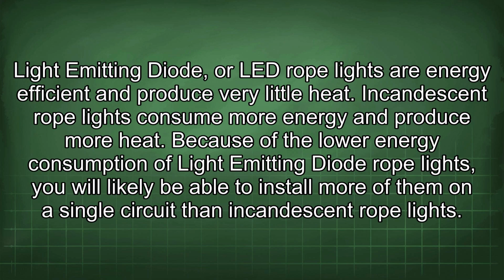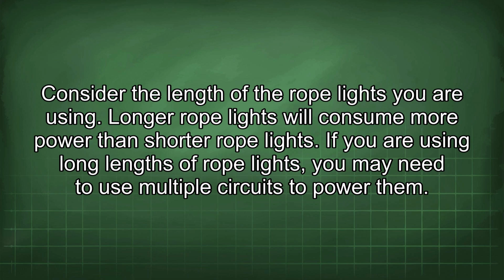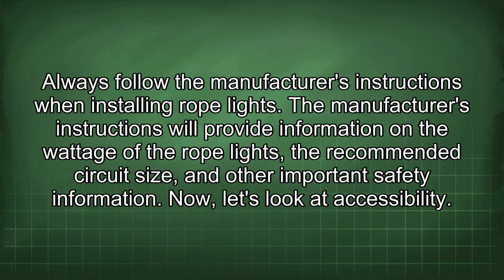Light-emitting diode or LED rope lights are energy efficient and produce very little heat. Incandescent rope lights consume more energy and produce more heat. Because of the lower energy consumption of light-emitting diode rope lights, you will likely be able to install more of them on a single circuit than incandescent rope lights. Consider the length of the rope lights you are using. Longer rope lights will consume more power than shorter rope lights. If you are using long lengths of rope lights, you may need to use multiple circuits to power them. Always follow the manufacturer's instructions when installing rope lights. The manufacturer's instructions will provide information on the wattage of the rope lights, the recommended circuit size, and other important safety information.